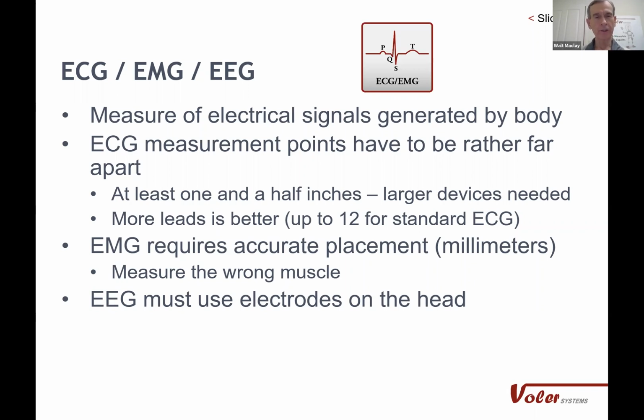One thing that I didn't mention here is on a wearable device, you'd like to have a dry electrode. Putting on the wet electrodes means each time you put the device on, you've got to get this electrode out. It's a little bit, it's wet. It's not so convenient. And it's going to dry out over time. It's much better if you just put the thing on and don't worry about the electrode. But dry electrodes don't make as good contact. They are successfully used. We've even worked with dry electrodes in pants that are able to measure the ECG signal while somebody's running, which is tricky. It takes some good signal processing, but it can be done.